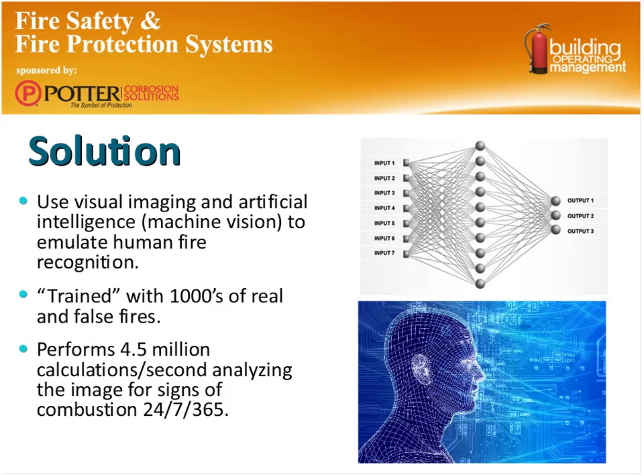So how do we do that? Well, you take electronic algorithms and you write those algorithms to simulate what a person's eye does, and then you train it. And if you train it through actual real fires, you can create a stored algorithm on board the camera that can take all those images, process them millions of times per second, and analyze all those pixels for evidence of change within that pixel. Once you understand what's changed, then it's just a matter of analyzing what that pixel saw: smoke, flame, motion. In the case of facial recognition, if there was a combined camera with that, it could actually pick out characteristics of an individual.